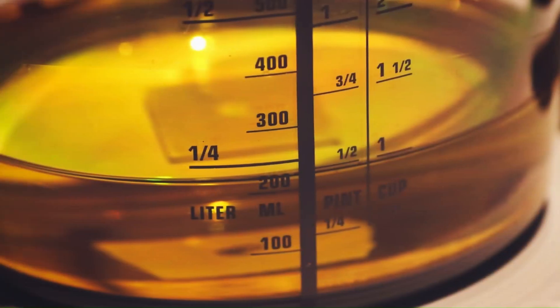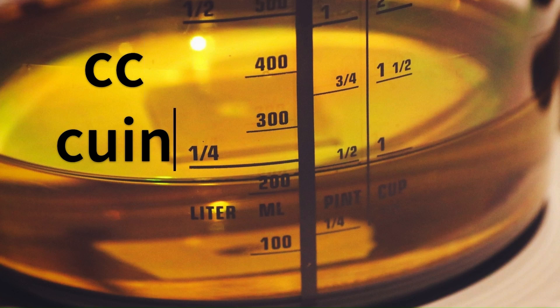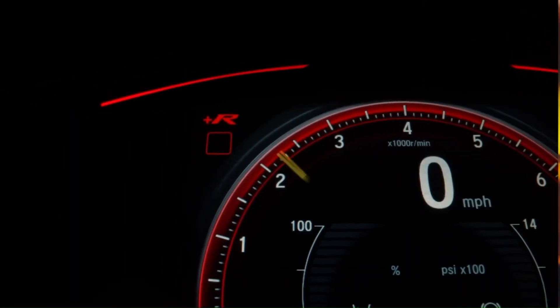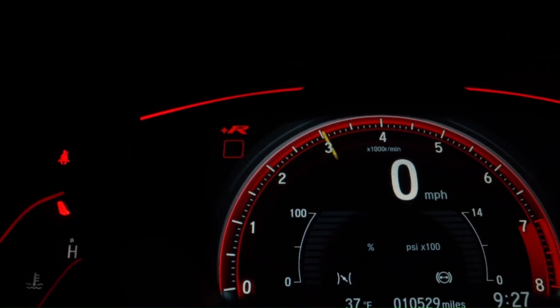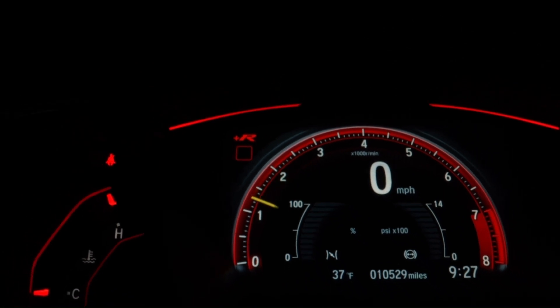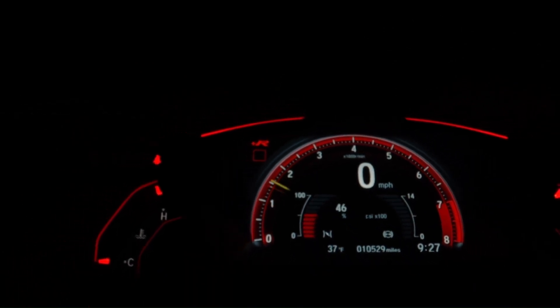A pump's displacement is the volume of oil that a pump pushes with every rotation. This is usually measured in cubic centimeters or cubic inches. Knowing the RPMs your motor will operate at tells us how many RPMs the pump will run at. This will help us determine the flow rate the pump can generate.